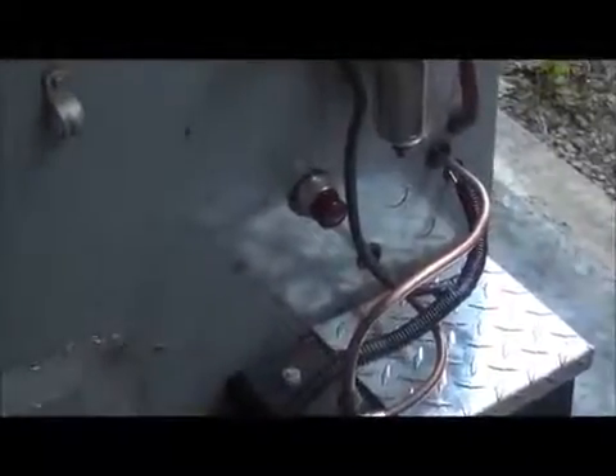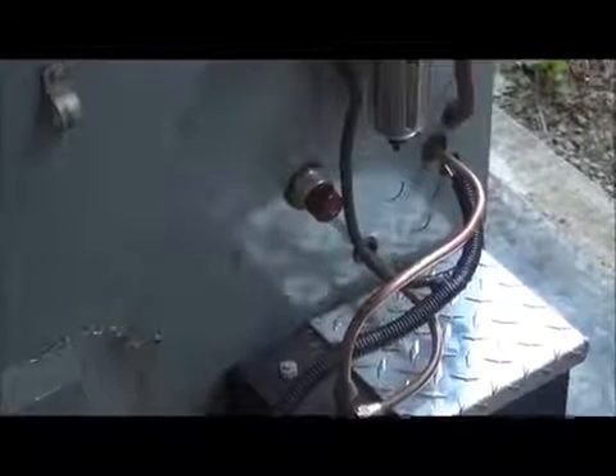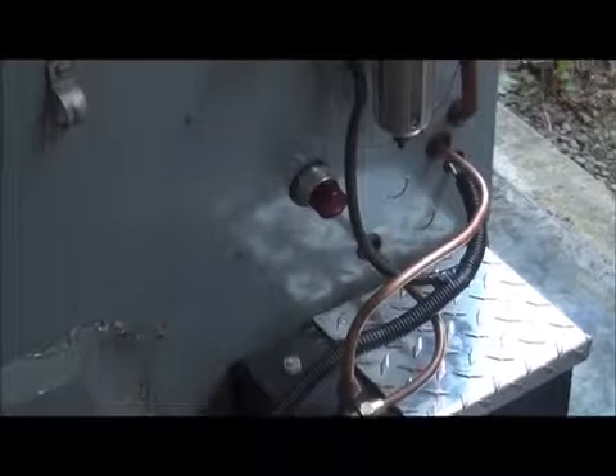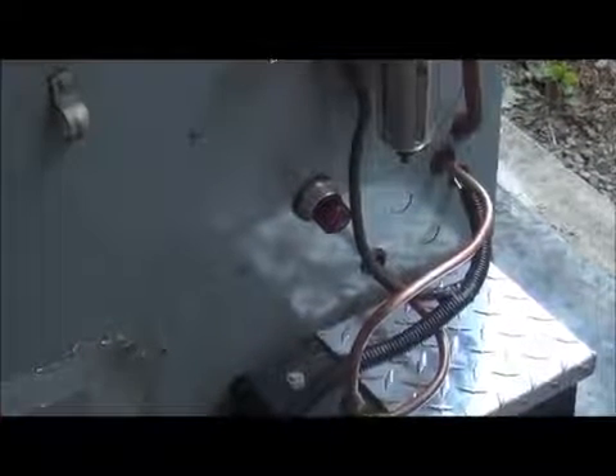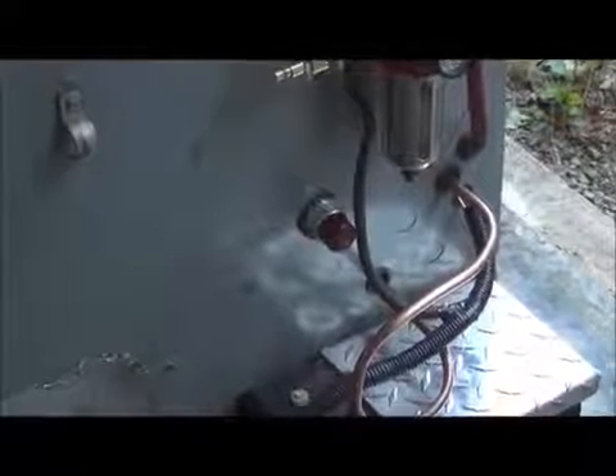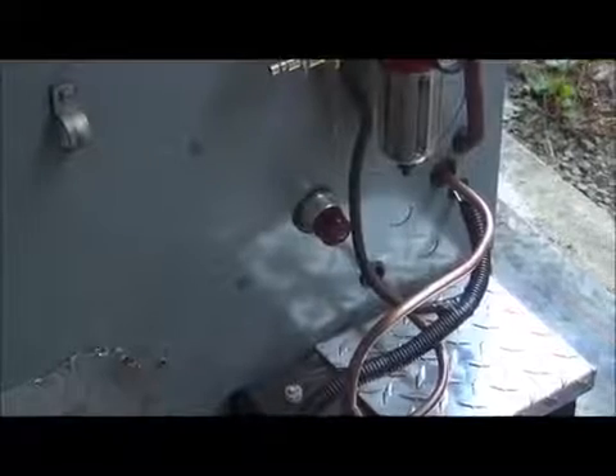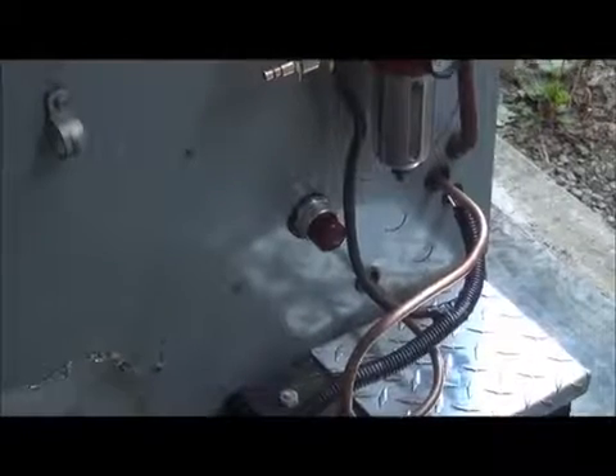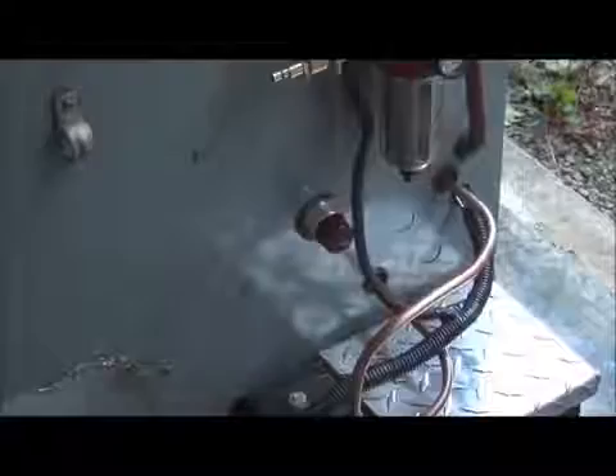What I have right here is a lighted push button switch, and this light comes on whenever the float switch engages the oil pump. So if I ever come out and notice that the light is on and my oil pump isn't running, then I'll know that the 20-second timer has timed out. That'll tell me that maybe my filter is clogged or that the float switch has failed or something like that. Pushing this push button switch resets that 20-second relay. So if I was ever to empty the tank to clean it out, and it actually did take more than 20 seconds to fill the tank up, I could just push this button a couple times to reset the pump and allow it to finish filling up the siphon tank.